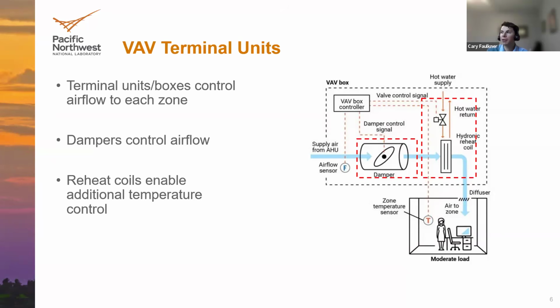And then the dampers will typically open and close to provide cooling as well as ventilation. And then reheat can be used to precisely control the heating needs at each zone, as typically, especially in large commercial buildings with core zones that don't have exterior walls, there's always going to be some amount of cooling needed as people and equipment generate heat, but then you can allow for reheat at those zones that maybe don't always need cooling and require heating.